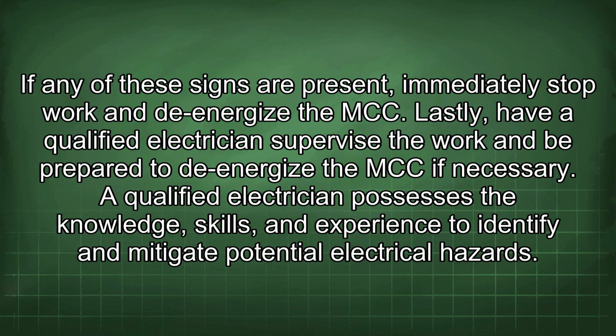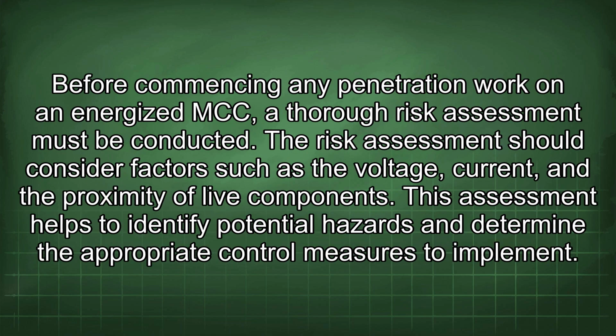Lastly, have a qualified electrician supervise the work and be prepared to de-energize the MCC if necessary. A qualified electrician possesses the knowledge, skills, and experience to identify and mitigate potential electrical hazards. Before commencing any penetration work on an energized MCC, a thorough risk assessment must be conducted. The risk assessment should consider factors such as the voltage, current, and the proximity of live components.